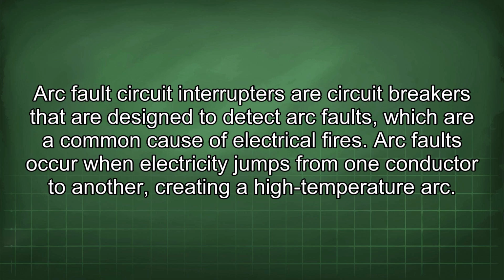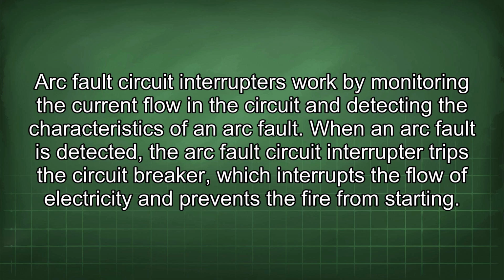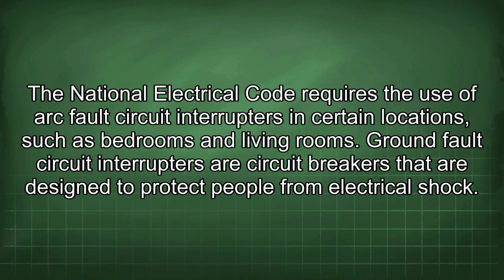Arc fault circuit interrupters are circuit breakers that are designed to detect arc faults, which are a common cause of electrical fires. Arc faults occur when electricity jumps from one conductor to another, creating a high-temperature arc. Arc fault circuit interrupters work by monitoring the current flow in the circuit and detecting the characteristics of an arc fault. When an arc fault is detected, the arc fault circuit interrupter trips the circuit breaker, which interrupts the flow of electricity and prevents the fire from starting. The National Electrical Code requires the use of arc fault circuit interrupters in certain locations, such as bedrooms and living rooms.